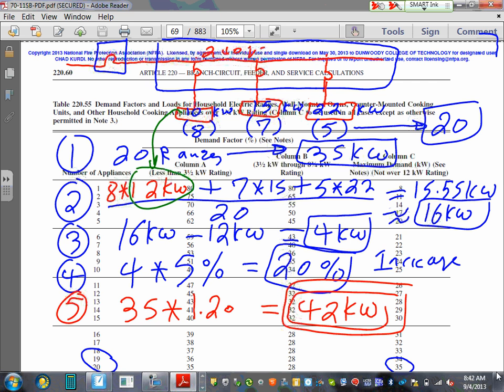That's their demand. But then now we need to up them. Up them by what? By the difference between their average and the 12. For every kW difference, they want you to increase it 5%. So the demand is 35 kW for ranges 12 or less, but if they are more than 12, then you need to average them. Anything less than 12, make it 12, average them. Then how far is the average from 12? Subtract 12 from 16. That's how far the average is from 12, 4 kW. For every 1 kW the average is more than 12, increase the demand 5%. That's what the language says. So we're 4 kW away from the 12. Increase it 5%. That will get you 20% increase. Then take your demand and up it 20%. 42 kW. Any comments, any questions?